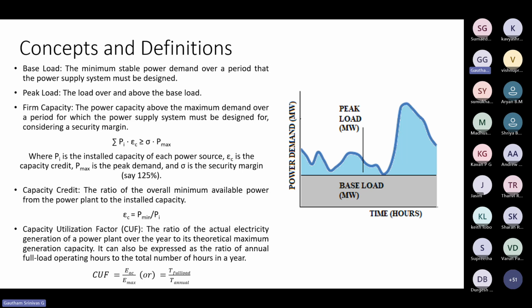The capacity utilization factor is the actual energy generated over the year versus the theoretical generation. So if you have a 1 megawatt solar power plant that's supposed to generate about 8760 megawatt hours in a year, but it only generates around 5 megawatt hours a day, then the capacity utilization factor is only about 20%.